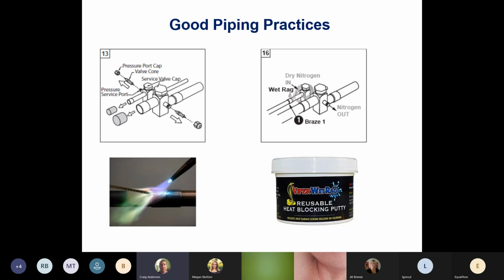So great stuff to have in your truck, especially if you're working on coils inside too. You know, the little stub that comes out of that plenum isn't very big. Wrap this stuff around as tight as you can. It's going to stop the heat from going into that TX valve. We get a lot of burnt out TX valves coming back. We start dealing with 7/8 and 3/4 inch copper, and it's being overheated and ruining the TX valve. So if you don't have this stuff in your truck, get a container. Like I said, it's going to last you all year.